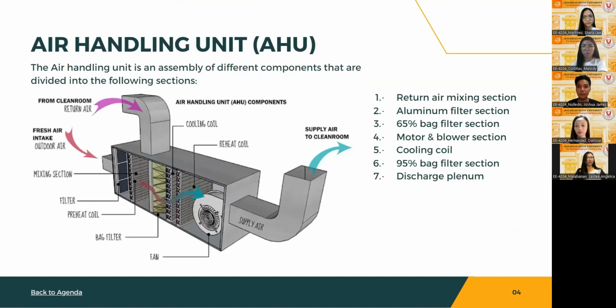The air handling unit is an assembly of different components that are divided into the following sections. We have the return air mixing section, aluminum filter section, the 65% bag filter section, motor and blower section, cooling coil, 95% bag filter section, and the discharge plenum. The supply return air sections of the AHU are connected via ducts to supply conditioned and filtered air to the respective zone. The room air is pumped into the return air mixing chamber of the AHU, where some fresh air is added, fresh air that is connected to the return air mixing chamber.